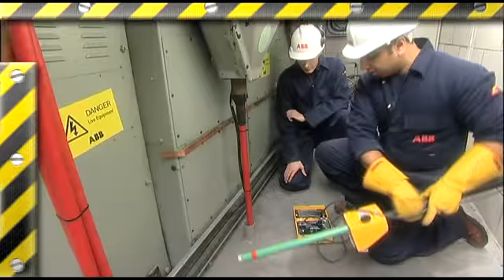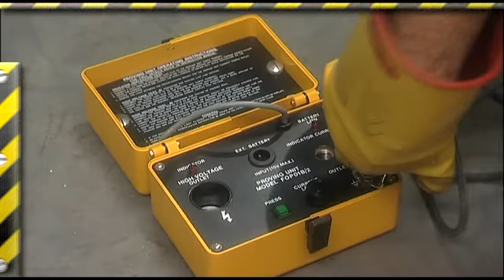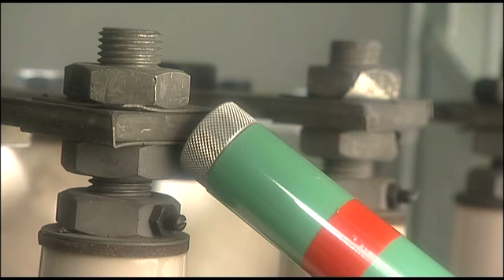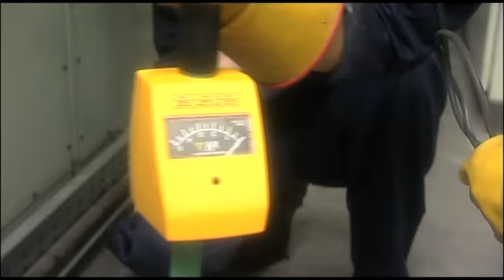Step 5. Check the installation is dead. This must be by means of a proper test instrument. Ensure you check that the tester is working before your tests. During the test, take precaution to keep clear of the connections. After the tests, recheck the test instrument.